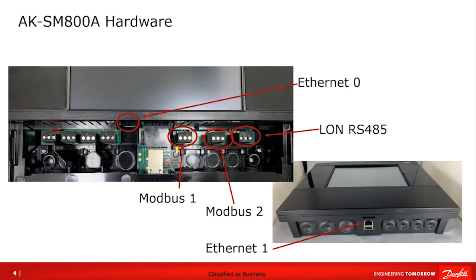Three plugs highlighted to the right would be plugs for downstream devices. Two plugs for Modbus communication and then a third plug for Echelon 485 communication. Each plug has three screw terminals — two for the communication wiring itself and a third for the shield. At the bottom of the unit is what we have labeled Ethernet one, a second Ethernet port. We do not want to plug a cable here for remote access — this port is dedicated to connections for downstream devices communicating back to our System Manager over an IP form of communication.